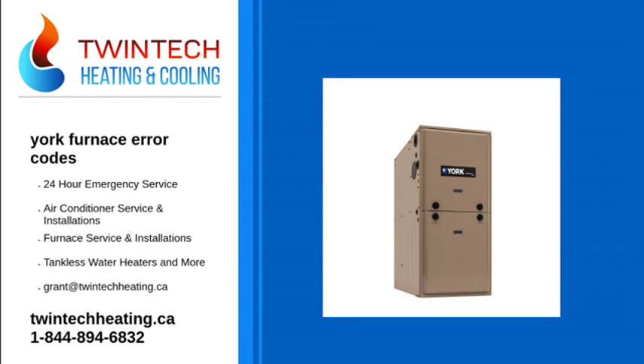Code: 9 red flashes. Result: indicates reversed line voltage polarity or grounding problem. Both heating and cooling operations will be affected. Check polarity at furnace and branch. Check furnace grounding. Check that the flame probe is not shorted to chassis.